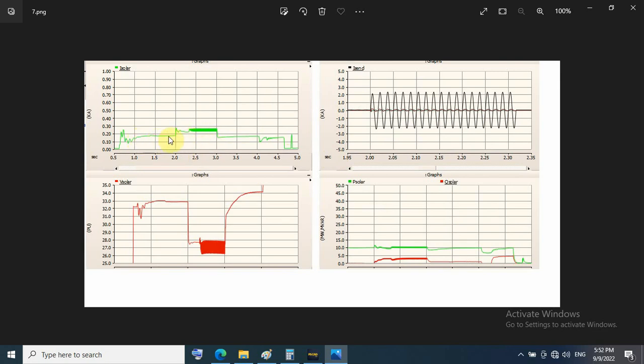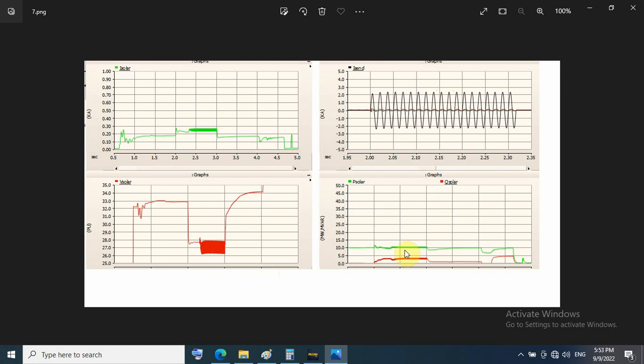The solar current increases with earth fault and decreases after fault clearing. From the grid side, the earth fault current is about 2 kilo-ampere peak-to-peak, that means 1.7 something kilo-ampere as RMS value. The PV reacts to this earth fault condition for voltage support to support the voltage on this bus bar. So this is the scenario for earth fault.